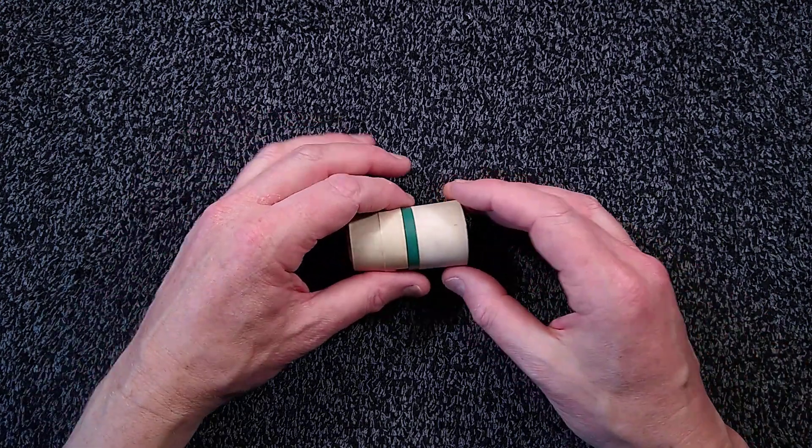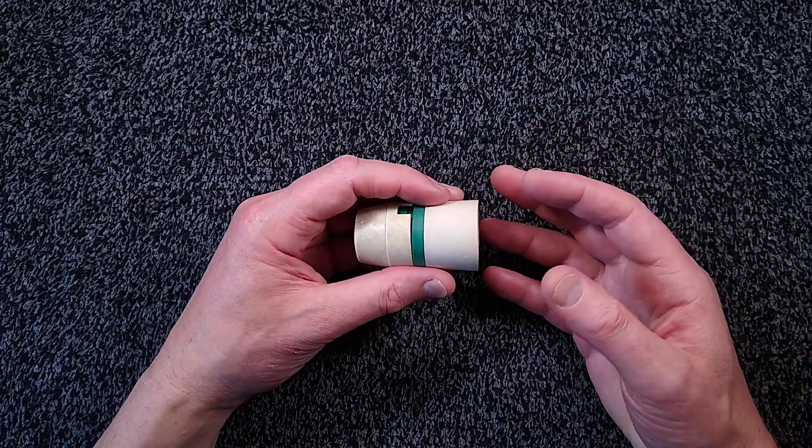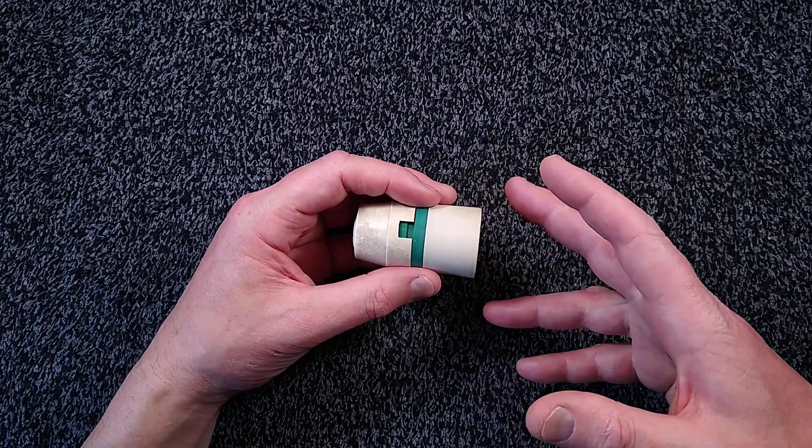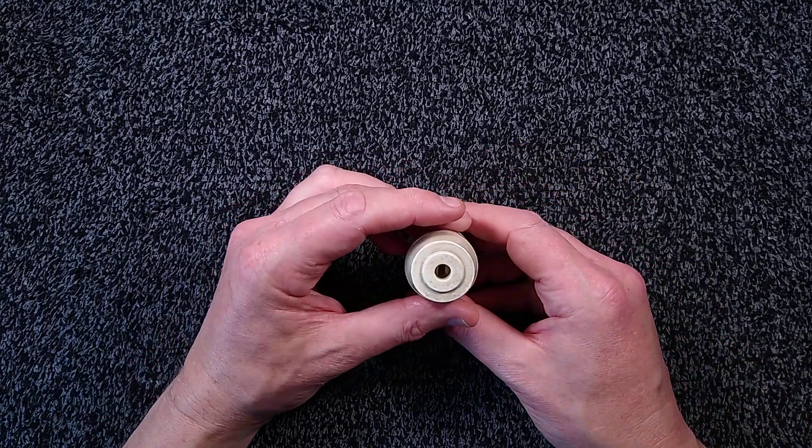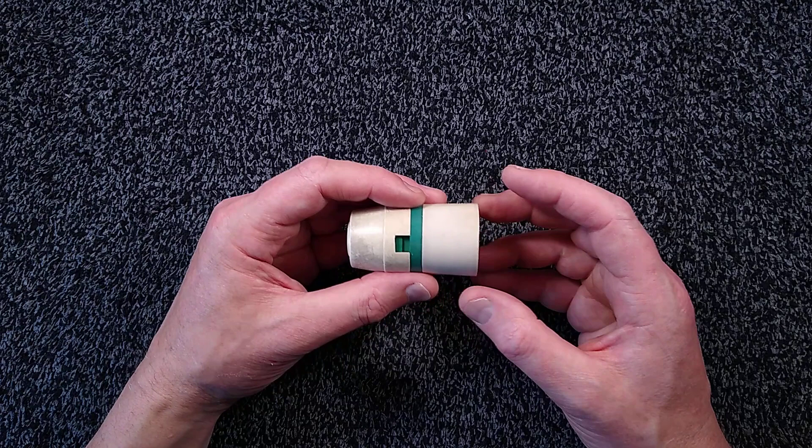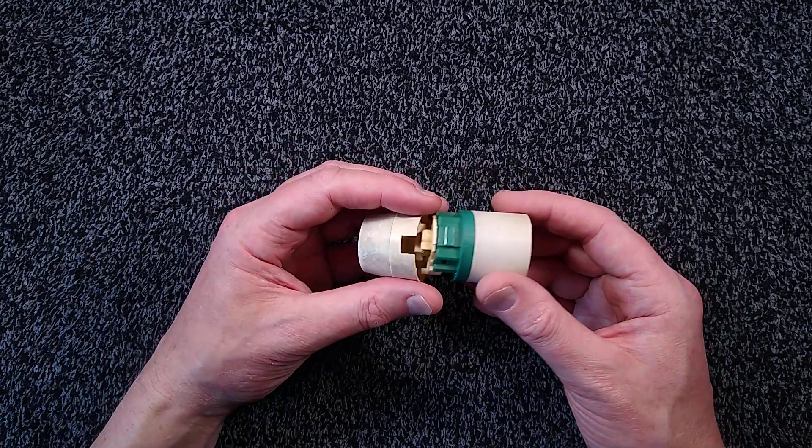This is quite an interesting thing. I'm in crew accommodation at the moment, and when we moved in there was one of the lights kept flickering in the hallway. So I fixed it by replacing the lamp holder because this existing lamp holder was arcing internally.